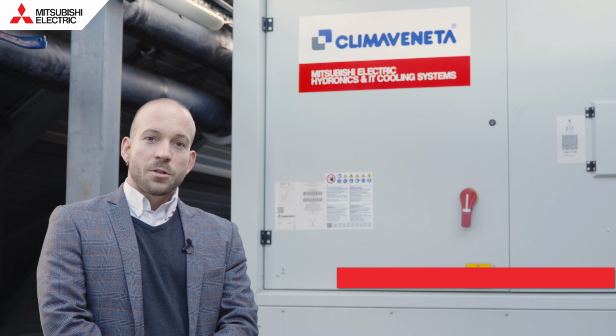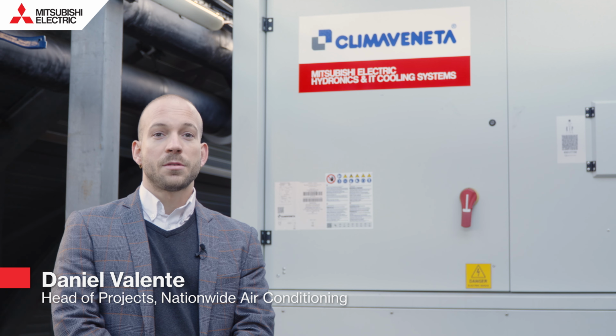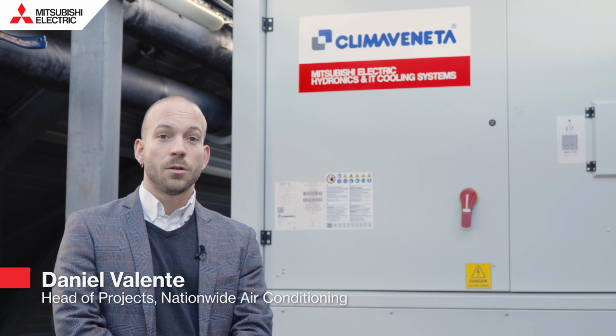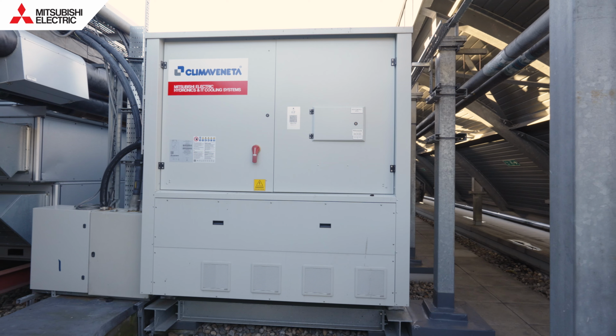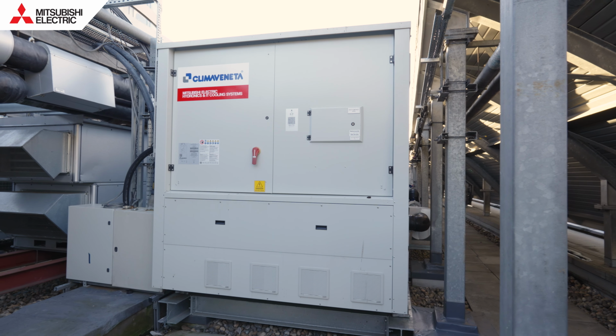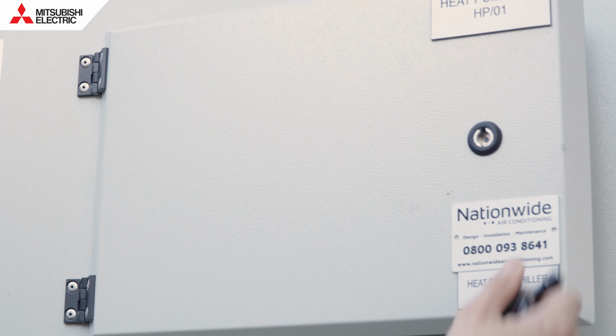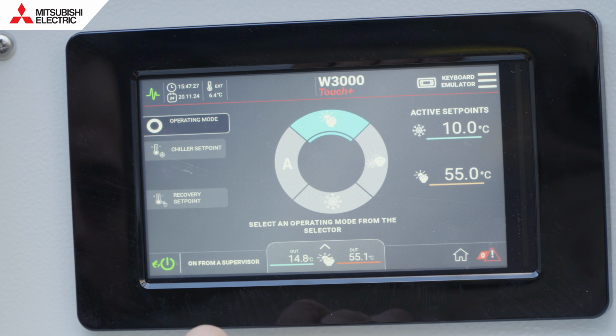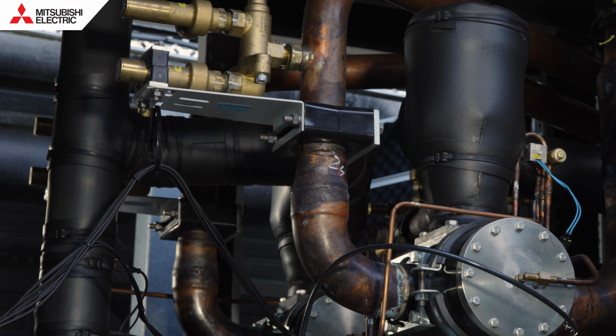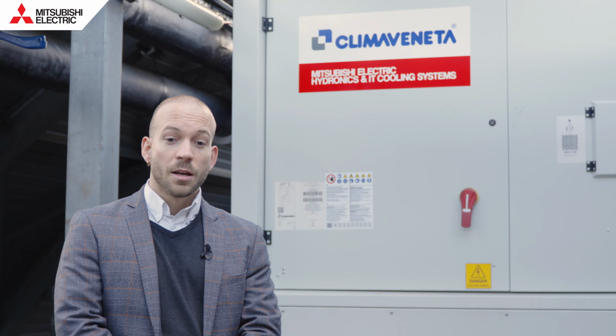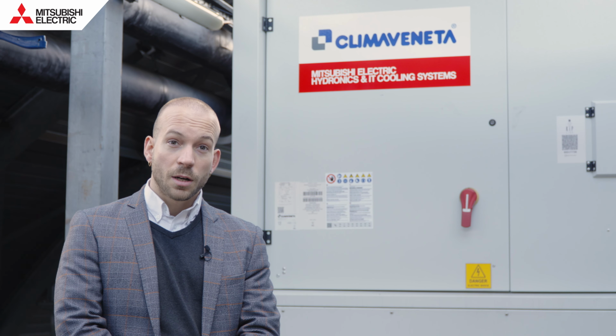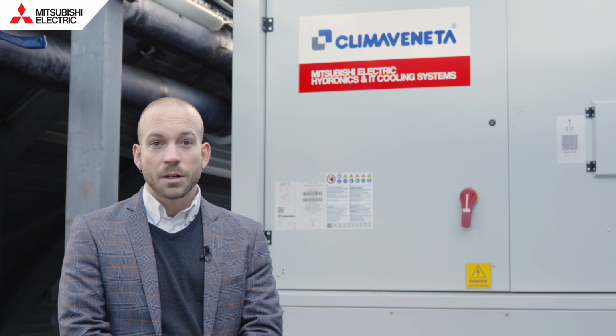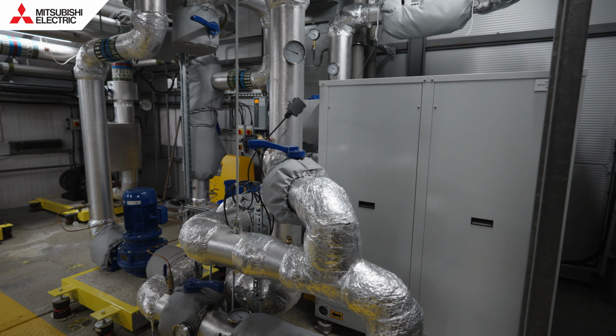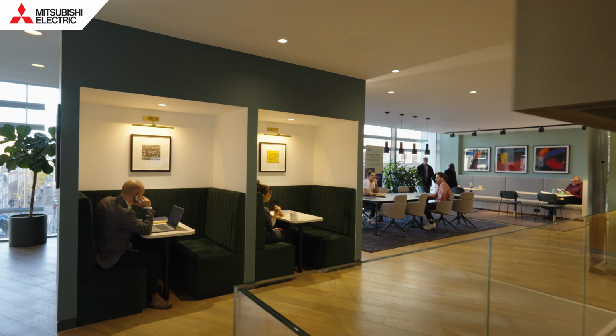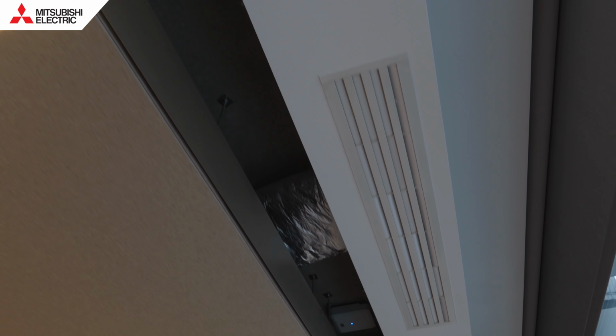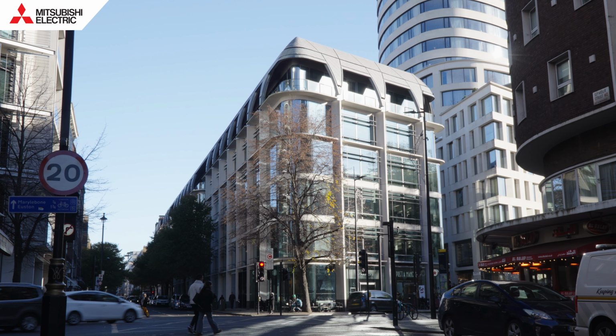The challenge around the project was to ensure that we could maintain a flow temperature hot enough to heat the building at all times. To do so, we needed a method for being able to increase the flow temp at periods of high load, which is why we installed a water-to-water heat pump. The unique aspect of this project was that we had no hydraulic separation and a much lower capacity on the water-to-water, so that we only injected the amount of heat required to give the building the load required during the winter months. The benefits of this were higher operational efficiencies, lower initial capital costs and a simpler installation.